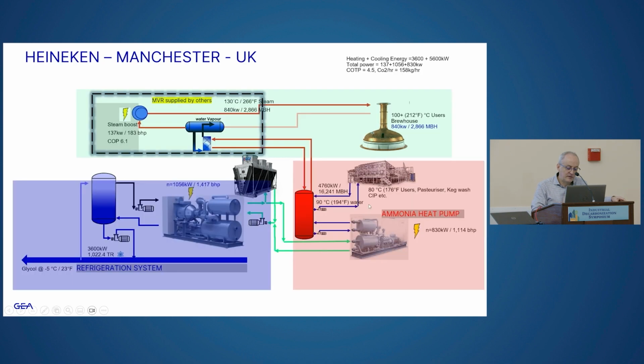So we converted that into a heat pump. We put in a heat pump making 90 C water, and the water goes to what is really needed, hot water, and then the water goes at 90 C, flashes, turns into steam at 90 C, and it's raised by MVR to almost 130 C or 260 F. And that's how they're making clean steam without any need of a boiler or a fossil fuel.